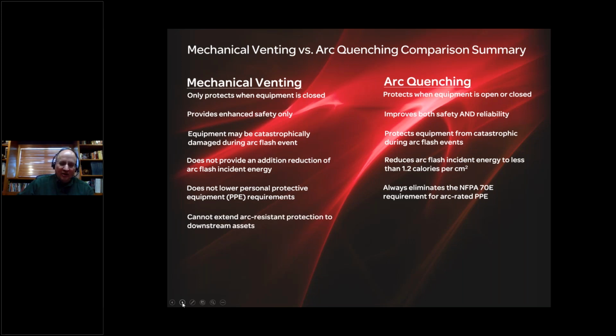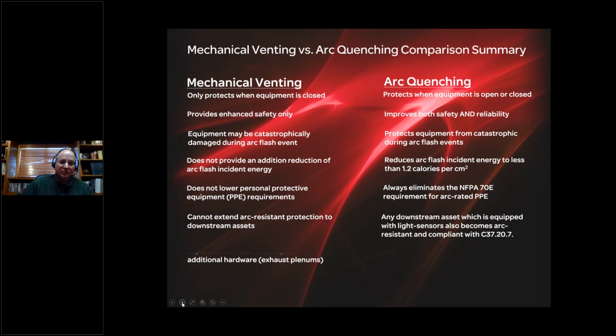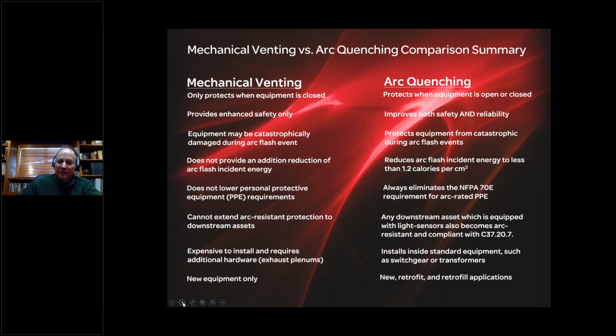You cannot extend the arc resistant protection to downstream assets, which is the subject of this presentation, and any downstream asset which is type tested and applied with light sensors becomes arc resistant per C37.20.7. And mechanical venting is expensive to install, requires additional hardware such as exhaust plenums, whereas arc quenching installs inside standard equipment such as switchgear or transformers. And mechanical venting is for new equipment only, whereas arc quenching works in new, retrofit or retrofill situations.